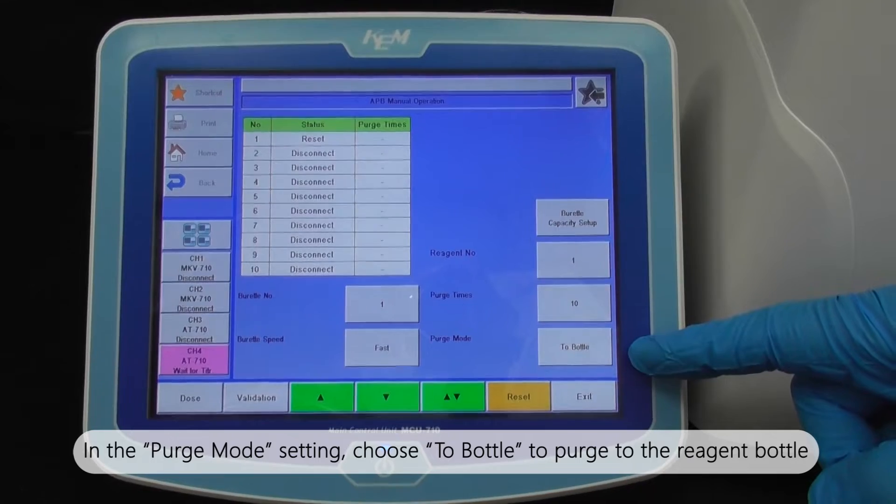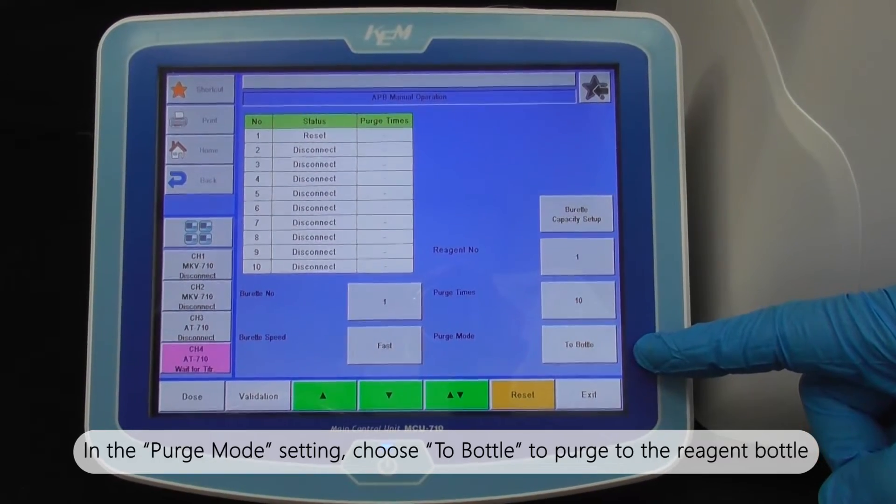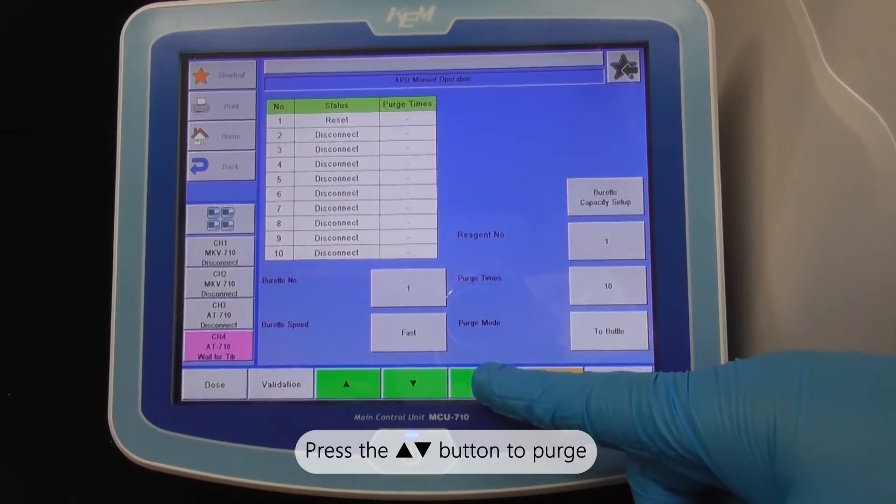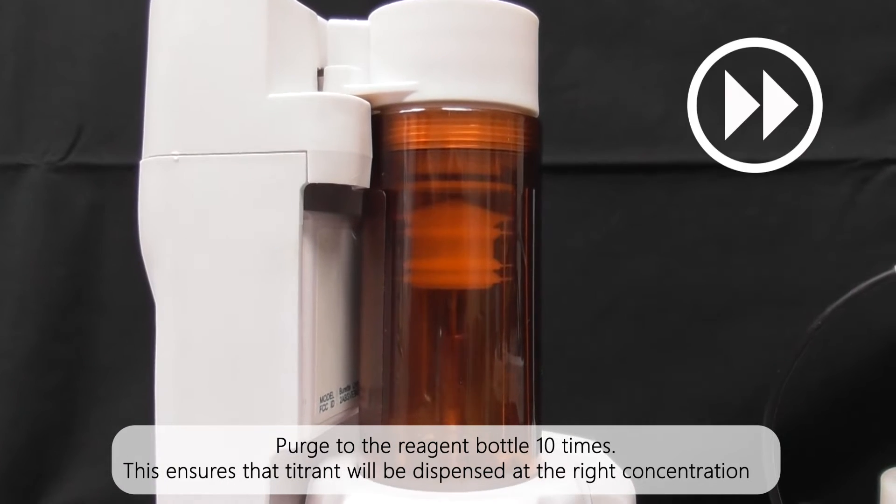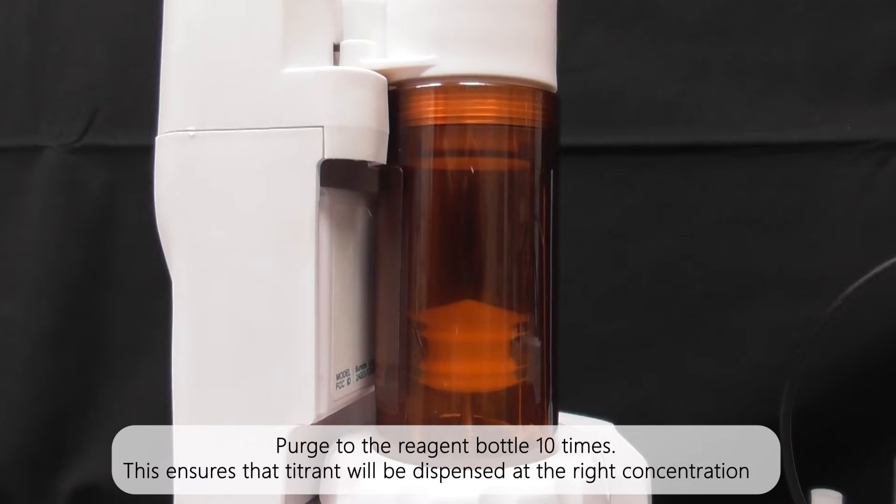In the purge mode setting, choose 'To Bottle' to purge to the reagent bottle. Press the up down button to purge. Purge to the reagent bottle 10 times. This ensures the titrant will be dispensed at the right concentration.